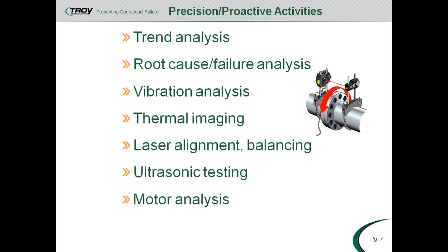Thermal imaging is an instrument which will take readings that can only be seen with the thermal imaging camera. It's the light waves that an eye cannot see. All bodies of any type of equipment above absolute zero emit infrared energy. Infrared energy is captured by a thermal imaging device, and it puts it into a visible image. Many of the thermal imagers today can capture a thermal image. They can also capture a digital image, and then we can put a voice print on it.